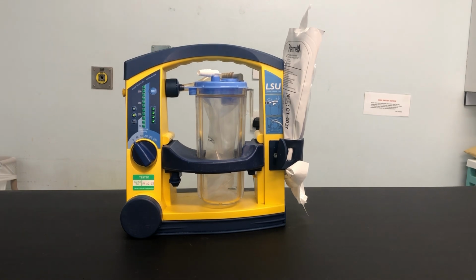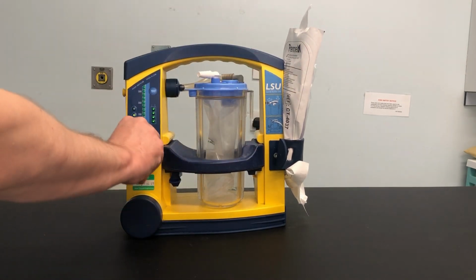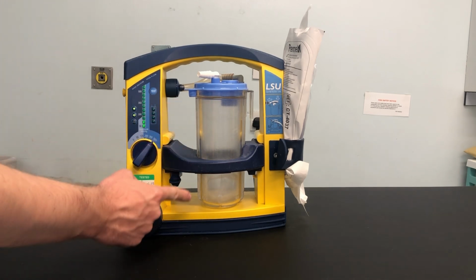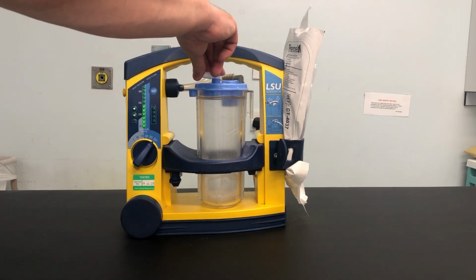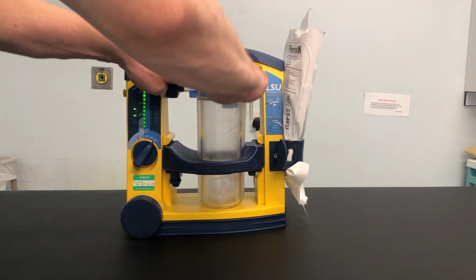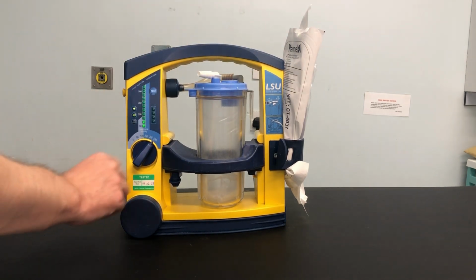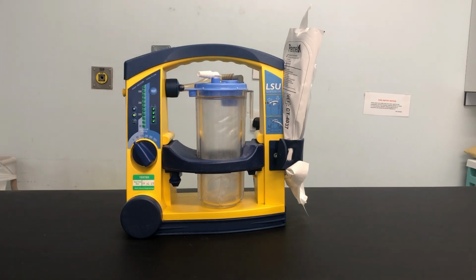Check that the lid of the canister is properly sealed by turning the operating knob to 500 millimeters of mercury. Block the white angle connector, patient inlet, with your thumb, and simultaneously push the lid down. Vacuum will build up when all parts are assembled correctly. Then remove your finger blocking that white angled connector, patient inlet, and make sure that the bag is fully in. Overflow of the suction materials can damage the device. Again, it is only recommended to fill to 700 ml. When the liquid reaches the top of the liner, the LSU will not suction any more liquid.